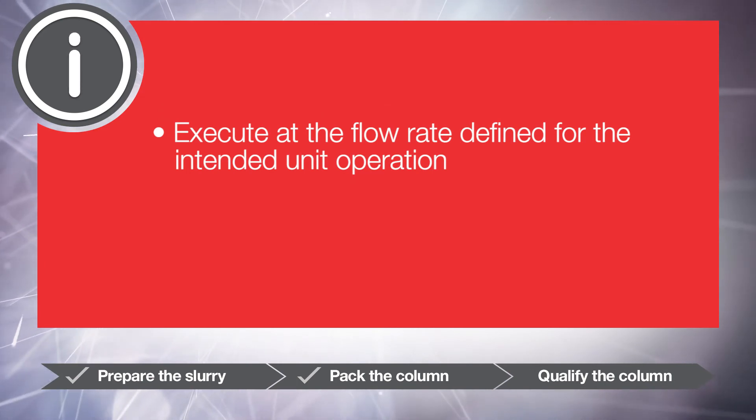If the packing buffer is different from the mobile phase, equilibrate the column for at least four column volumes with the mobile phase. Execute at the flow rate defined for the intended unit operation, typically 100 to 300 centimeters per hour. Monitor conductivity for sodium chloride. Qualification results depend on a number of factors, including the solutions and method used, scale, column hardware, and chromatography system. After you define a column qualification procedure for a specific system, column plus chromatography system, base the qualification acceptance criteria on historical values and ranges instead of theoretical qualification results. Performing the column qualification method consistently and reproducibly is critical to obtaining meaningful results.